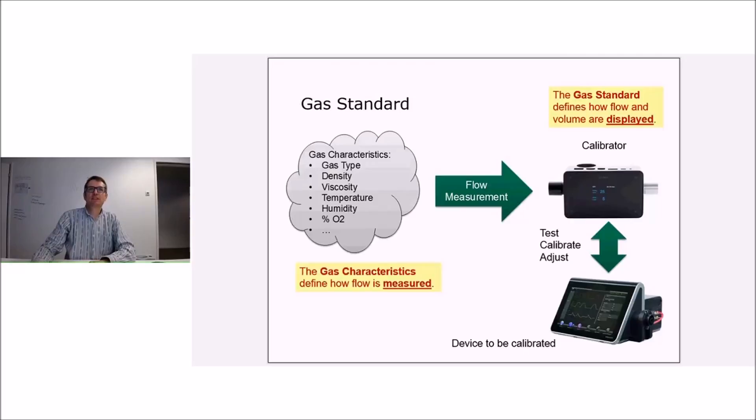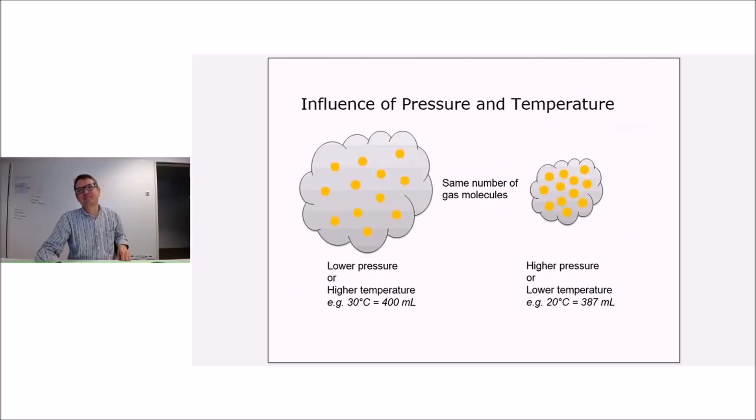Gas characteristics define how the flow is measured, and the gas standard defines how the flow is displayed. Well, now comes the different influences of pressure. You all know that a gas at a higher temperature or a lower pressure takes up more space, and all this is taken into account by the PF300. So a gas cloud with a number of molecules might be much bigger at 30 degrees Celsius than it is at 20 degrees. What we can see here as an example.